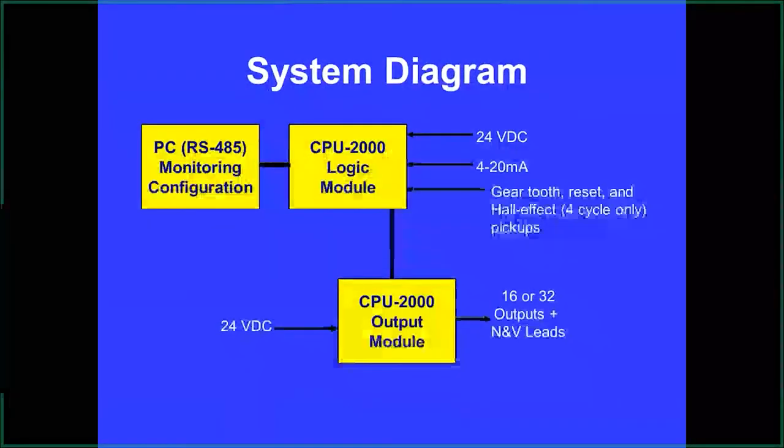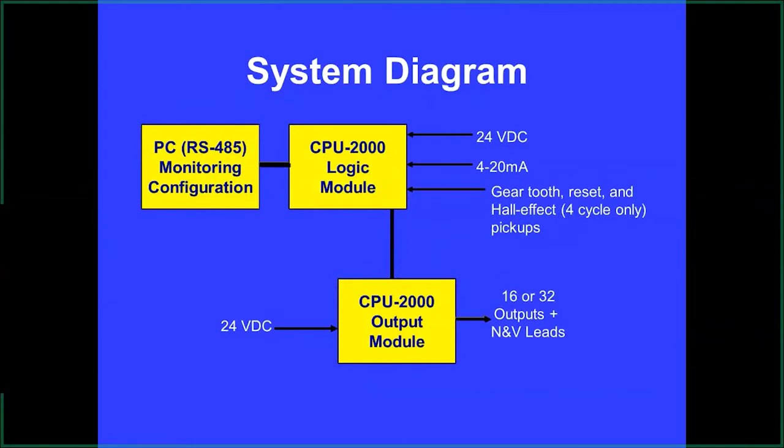To program it we use a PC or a laptop with an RS-485 connection in the logic module, which can also be brought out into a PLC if you want to monitor the register numbers. We require 24 volts to power it. If you want to change timing from a PLC or remote source, it accepts a 4-20 mA input — needed for large low-speed engines that require advancing ignition well past top dead center to boost the turbochargers.